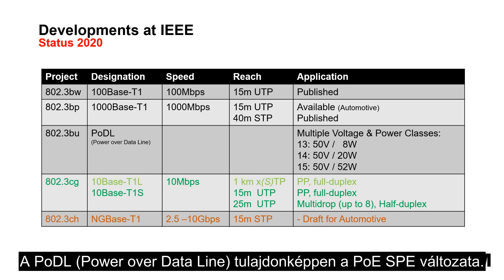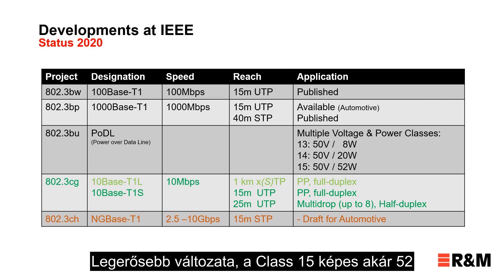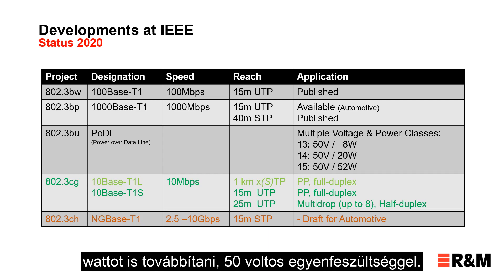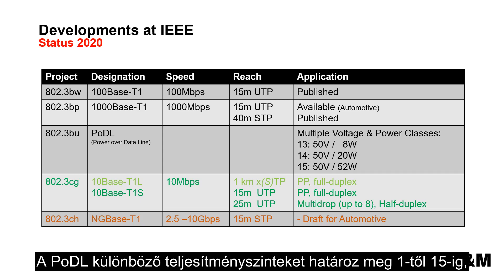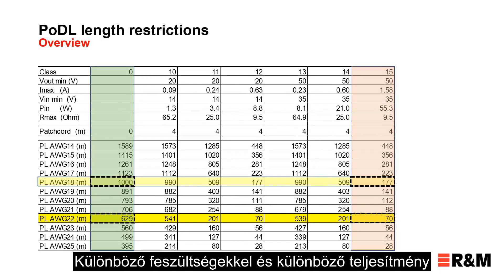PoDL — Power over Data Line — is the SPE version of PoE. It provides power over the same line as data. In its most powerful version, class 15, it is able to deliver up to 52 watts with a DC voltage of 50 volts. PoDL defines different power levels, 1 to 15, with different voltages and power levels.